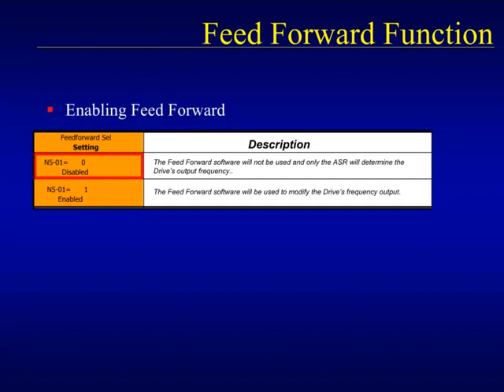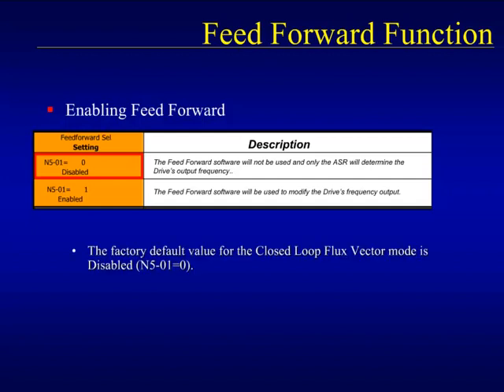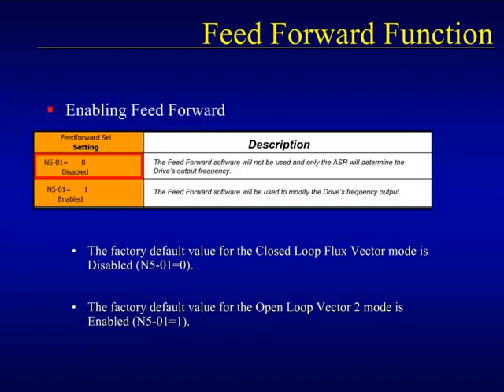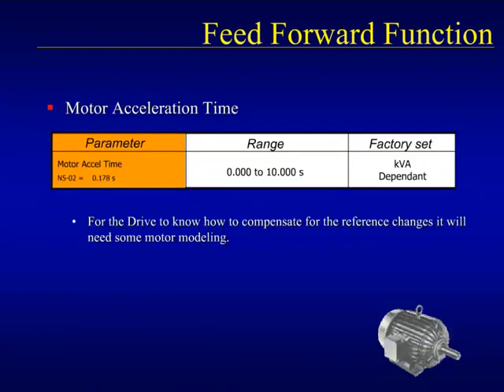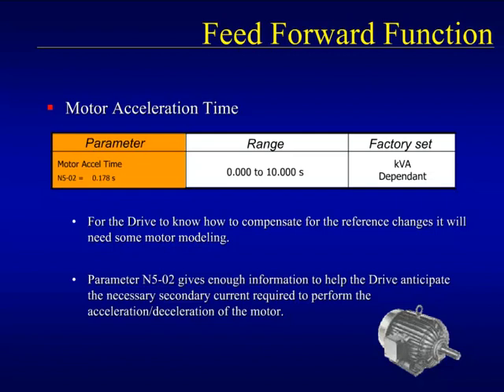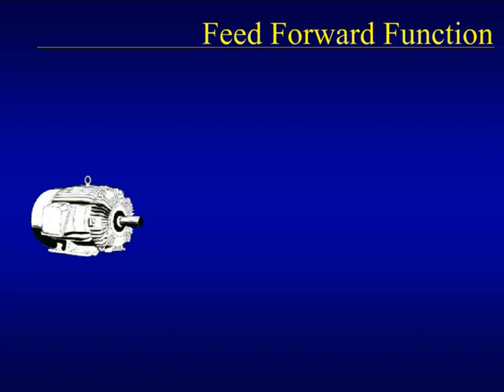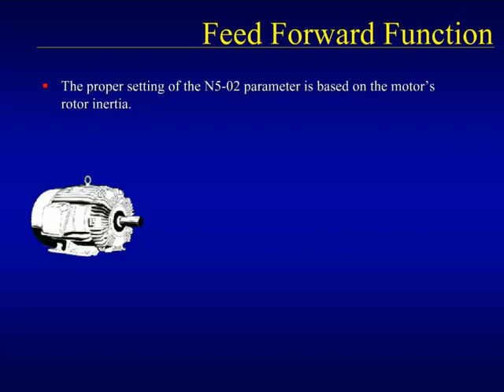The first step to using the feed forward function is to enable it. Parameter N5-01 will turn the feed forward circuitry on and off. If the drive is configured as a closed loop flux vector controller, then the default setting of the feed forward function is off. If the drive is configured for the open loop vector 2 control mode, the default setting of the feed forward function is on. Feed forward is not available in the other drive control modes, including the open loop vector 1 mode. The key to effective feed forward use is to accurately program information about the motor into the drive. The setting of parameter N5-02 is necessary for the feed forward function to compensate for the torque necessary to accelerate the motor's rotor inertia. N5-02 is set in terms of acceleration time and is based on the inertia presented by the motor's physical components such as the shaft and rotor.